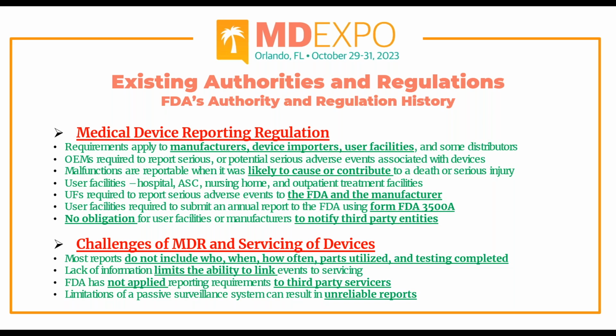Challenges of medical device reporting and servicing. Most reports do not include who, when, how often, parts utilized, and what testing was completed. So if you're looking at user facilities or healthcare organizations, when they do a report on an event that could have or did result in serious injury or death, none of that information is required to be included. The lack of information limits the ability to link the events to services. This device caused this problem, resulted in this outcome. You can look through and gather all that data and information, but there's no link back to services. It's only that the device malfunctioned, and this was the result. Nowhere in there does it say this is who serviced it, this is the last time it was serviced, and these are the parts that were used.